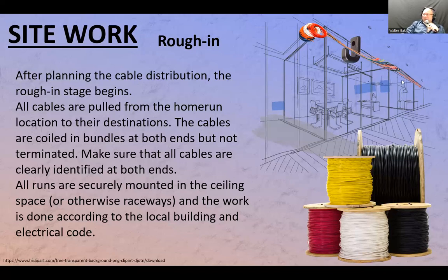Now, how do you establish a straight run? After the whole shebang is there in the ceiling and the thing is packed, you're going to look for straight lines that you can go from here to here. You tie your string to one spot that you think you can establish a straight line, and you run the string, the twine, from that box along the ceiling. Then at the other end, you pull it snug and go, yeah, there we go, we got a straight line. So you mount that string right at that spot.